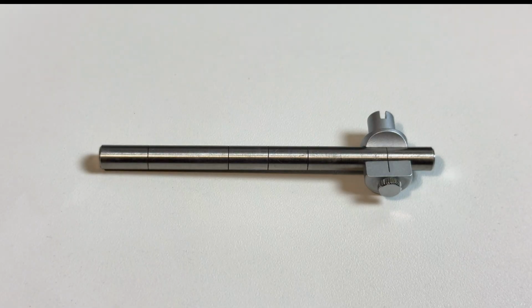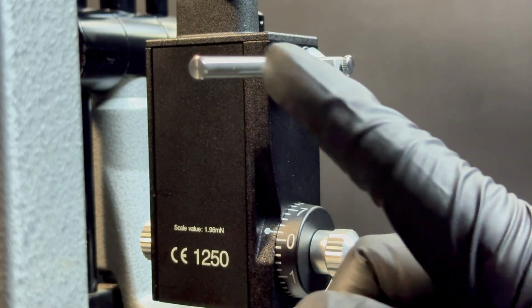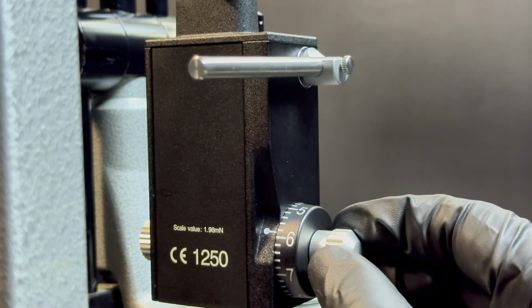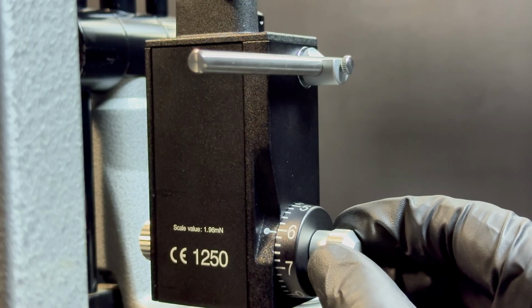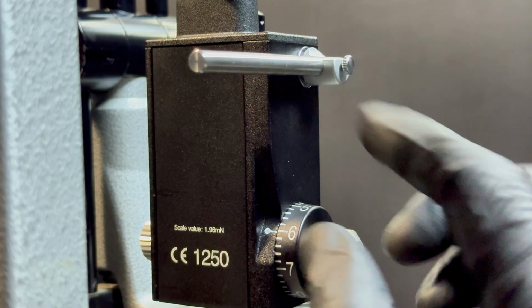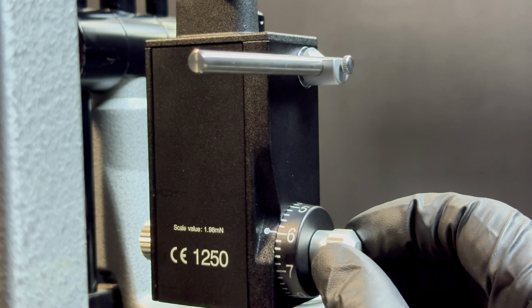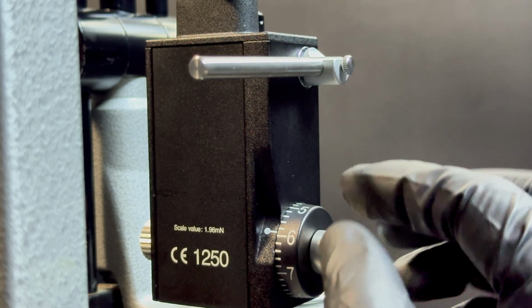We are now going to check the calibration at the 6th setting. Set and secure the weight at the 6th position on the calibration bar. Again, make sure the longer end points towards the examiner. At 6.05, the feeler arm should move toward the stop in the direction of the patient. At 5.95, the feeler arm should move toward the stop in the direction of the examiner.